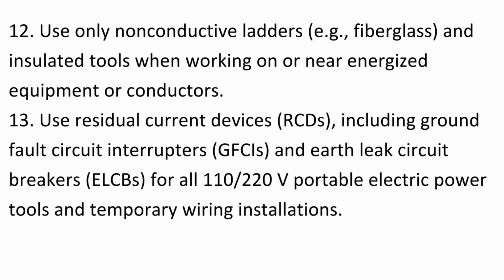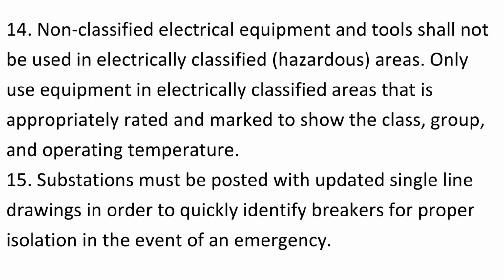12. Use only non-conductive ladders, for example fiberglass, and insulated tools when working on or near energized equipment or conductors. 13. Use residual current devices, RCDs, including ground fault circuit interrupters, GFCIs, and earth leak circuit breakers, ELCBs, for all 110-220V portable electric power tools and temporary wiring installations. 14. Non-classified electrical equipment and tools shall not be used in electrically classified, hazardous areas.